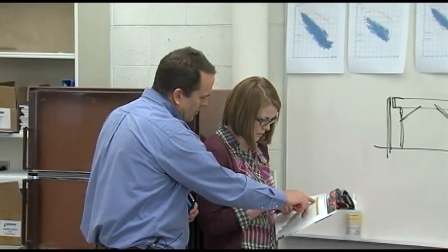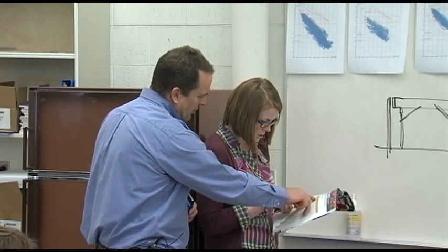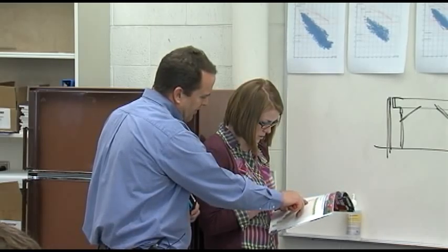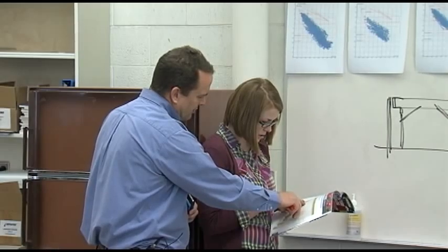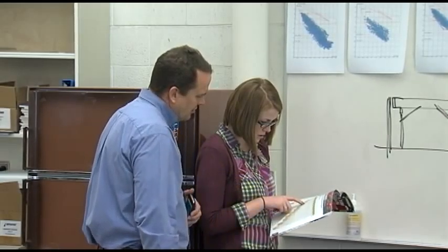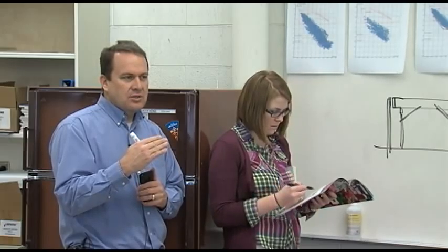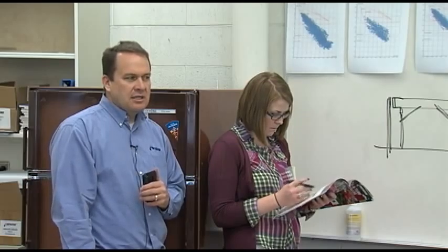So there's our velocity. This number here, as soon as it goes to 7, oh, so we need a 1 inch, right? Because that's 7 right there. Yeah. So see how there's that lighter color on the velocity per second in there, and I said you couldn't go over 7.5 feet, so you just go right down to 7.5, or that number before it changes, and that's actually where it changes colors. So it's that tan color, so we know that it's the 1 inch. Does that make sense? Can you see that?